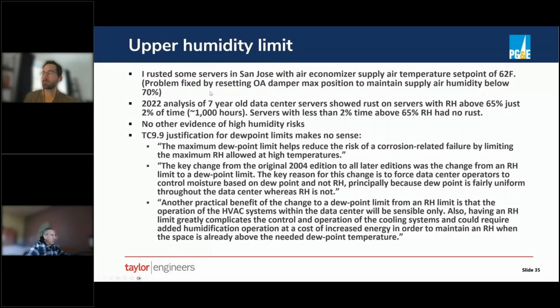And there isn't a lot of data out there, but we have some anecdotal data from our own experience. We've seen literally cases where the servers can start to rust. If you maintain a high enough relative humidity for long enough, the servers will start to rust. We were supplying very cold air using an air economizer at 62 degrees, which meant that a lot of the time that air was being supplied at a relatively high RH. And that gave us this problem of rusting. We solved that problem pretty quickly by simply raising the supply set point, which effectively lowers the RH.